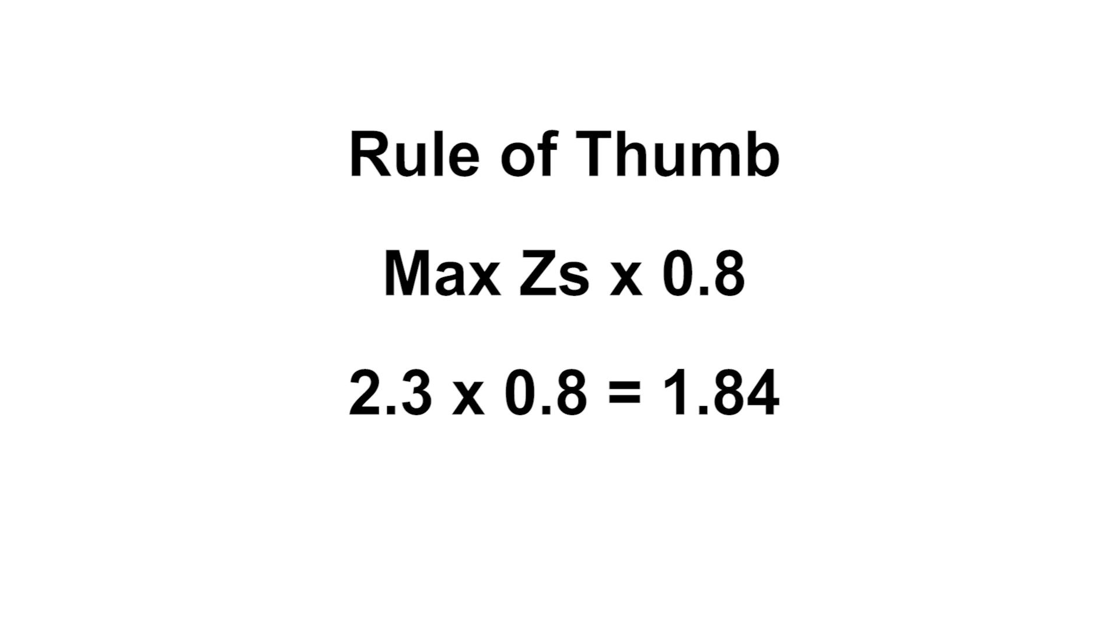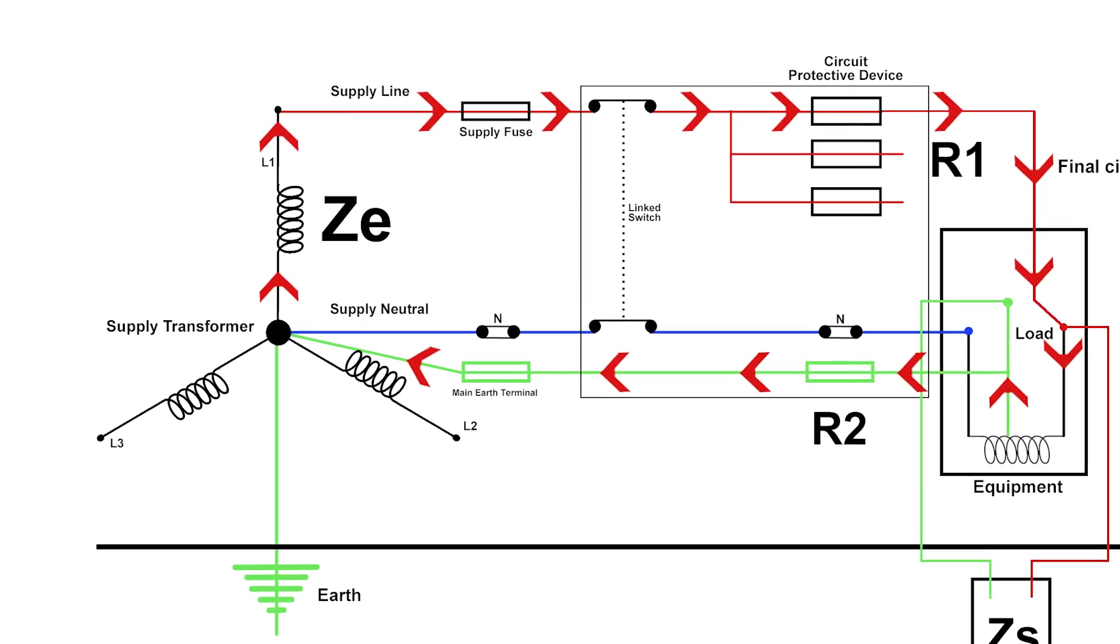We know that the maximum we can operate at—or maximum temperatures our cable can run at—are 70 degrees, but we've no idea the temperature of those cables when we're measuring them. For our purposes, if we multiply the maximum value from BS7671, which for a 20 amp type B device is 2.3 ohms, by 0.8, we end up with a value of 1.84. Our measured value must not be greater than that rule of thumb value.